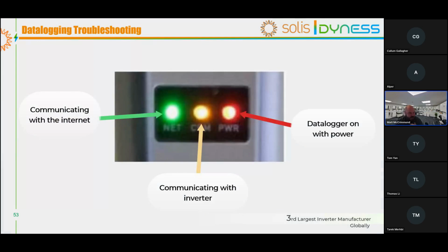Once you've connected your data logger, we have some form of troubleshooting you can probably do yourself on site. We have 3 lights on all our data loggers, whether or not it's horizontal or vertical. They all indicate the same stuff. One is green. Green means that it's connected to the internet. So for example, if you had the amber light and the power light on, but no green light, then you would find that the issue is that you can't connect to an internet source. If you see that flash blinking really fast, it's trying to connect to the internet, but it's not able to do it. So it's probably an issue on your end.